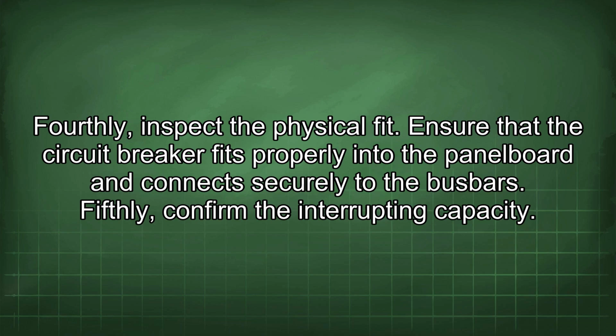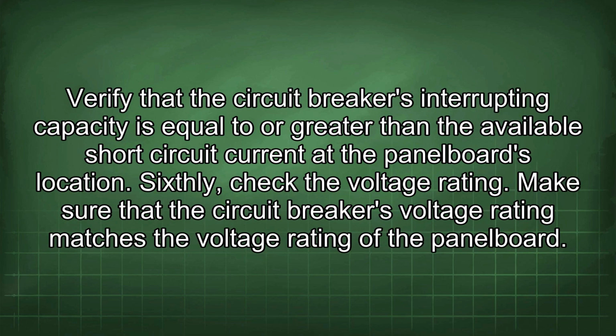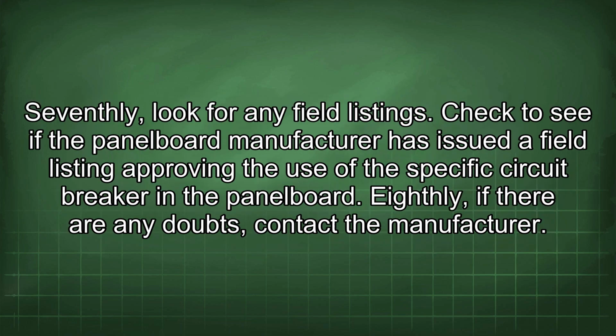Fifthly, confirm the interrupting capacity. Verify that the circuit breaker's interrupting capacity is equal to or greater than the available short circuit current at the panelboard's location. Sixthly, check the voltage rating. Make sure that the circuit breaker's voltage rating matches the voltage rating of the panelboard. Seventhly, look for any field listings.